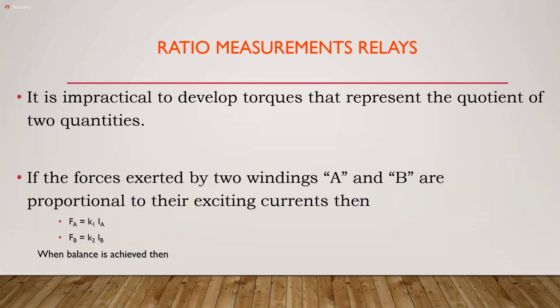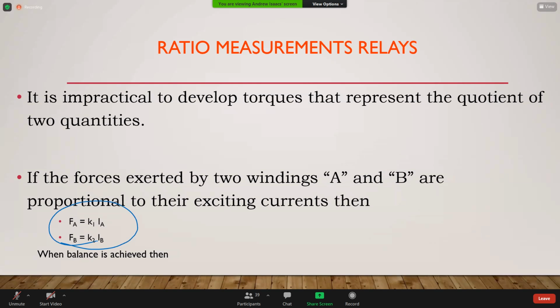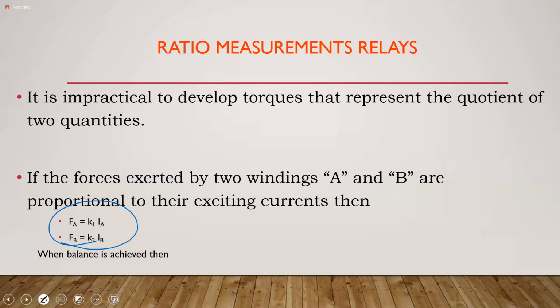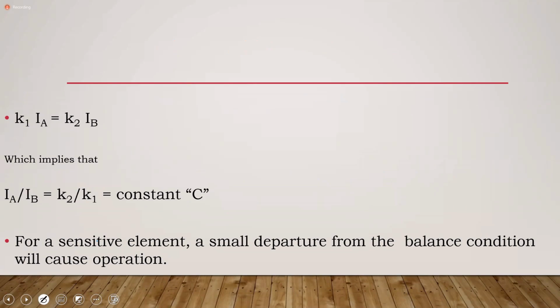But if we have the forces exerted by two windings, and these forces are proportional to their exciting currents, then this relationship would be true. When balance is achieved, it means that the two forces would be equal. This principle is what we call the balance beam principle. So the two forces, when they are equal, would establish a balanced beam. We have it exerted at either end based on the two coils. When balance is achieved, this is true.